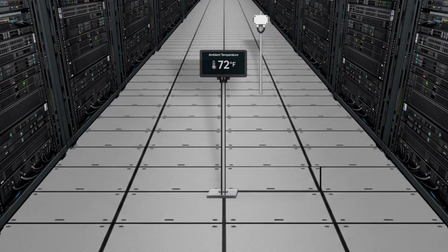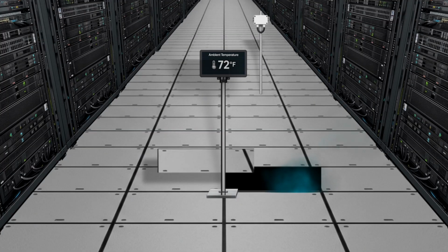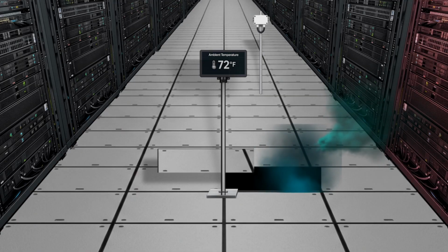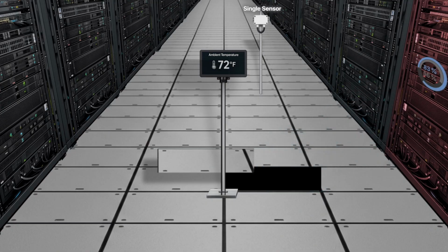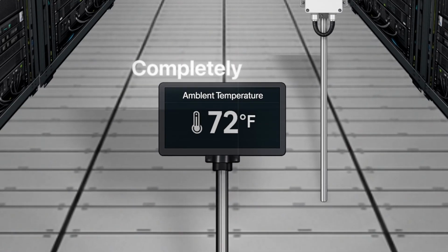Now, data centers are always designed around airflow. Cold air comes up through the raised floor, travels through the front of the racks, absorbs heat from the equipment, and exits out the back of the hot aisle. When that system is working correctly, everything stays within a safe operating range. But when airflow breaks down, hot exhaust air from the back of one rack recirculates around to the front intake of the next one. That localized heat buildup can push equipment temperatures well above the safe threshold, while the ambient sensor on the wall reads completely normal.